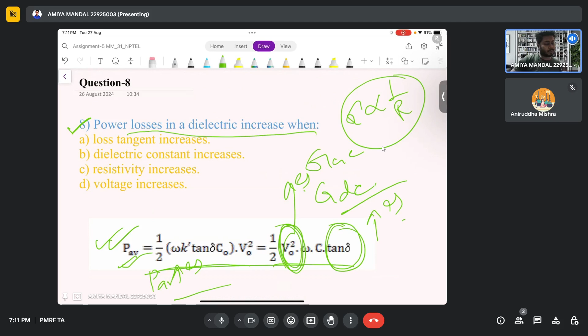G is nothing but the conduction value. So we consider everything, and finally the average power comes to this point. You can see it depends on tan delta and the average voltage. So when does the power loss in the dielectric increase? It depends on when tan delta increases and when voltage increases. If voltage increases, it increases with the square value, which means the voltage increment factor is very important. So the loss tangent, tan delta, increment gives power loss increment.